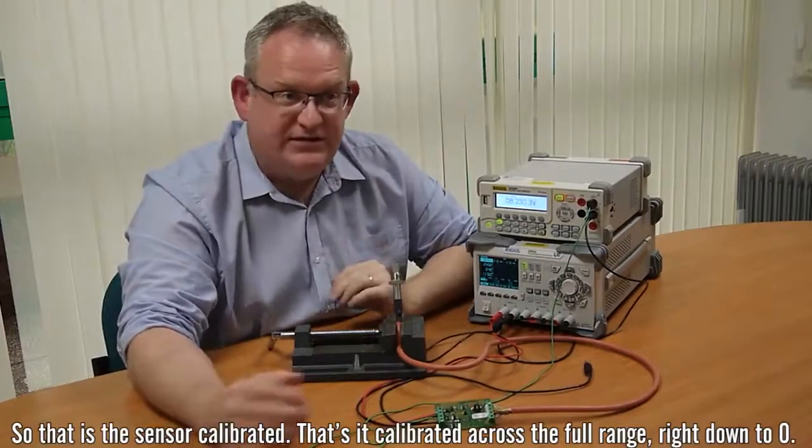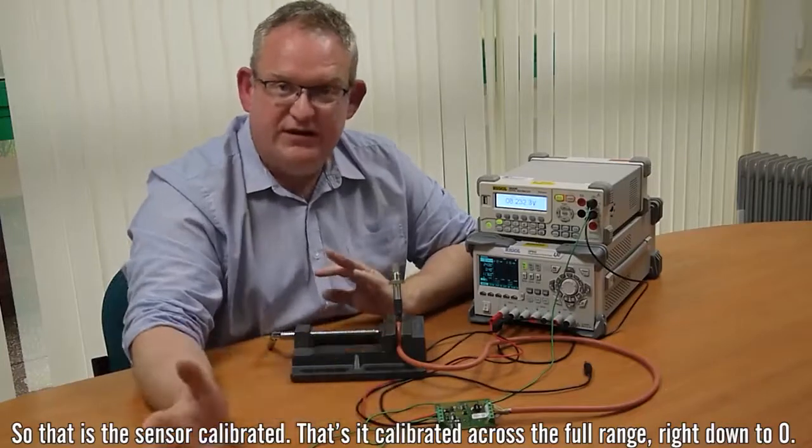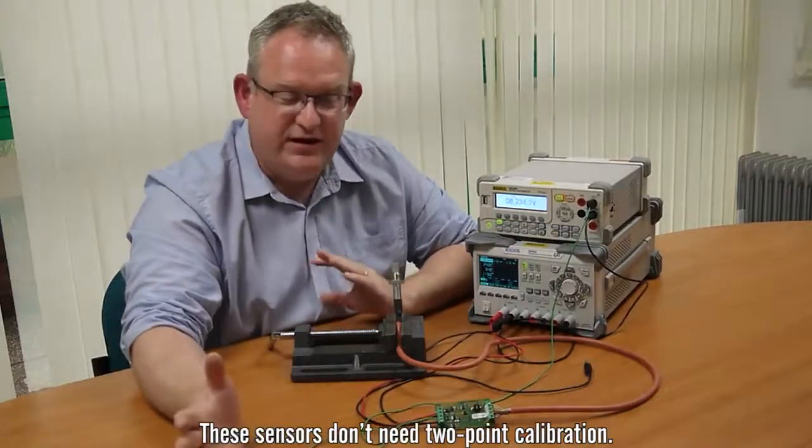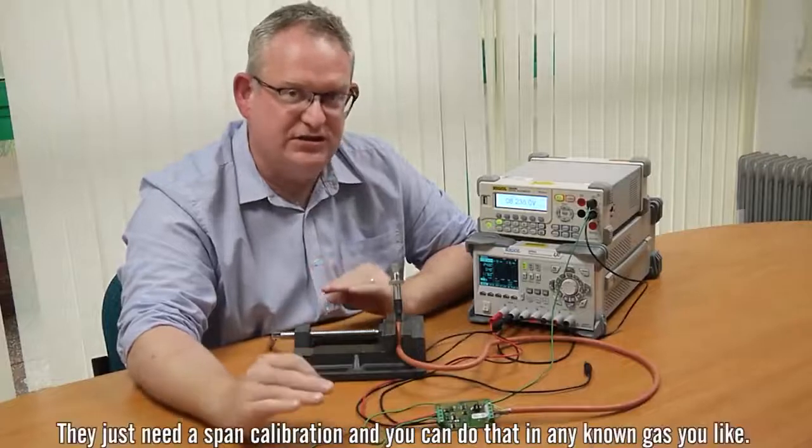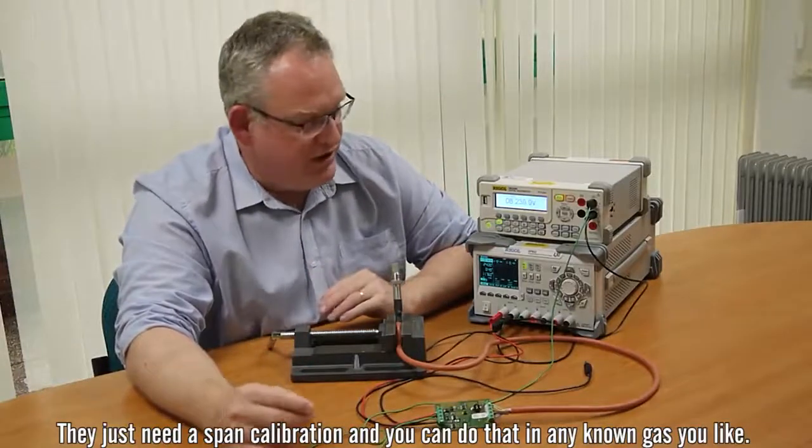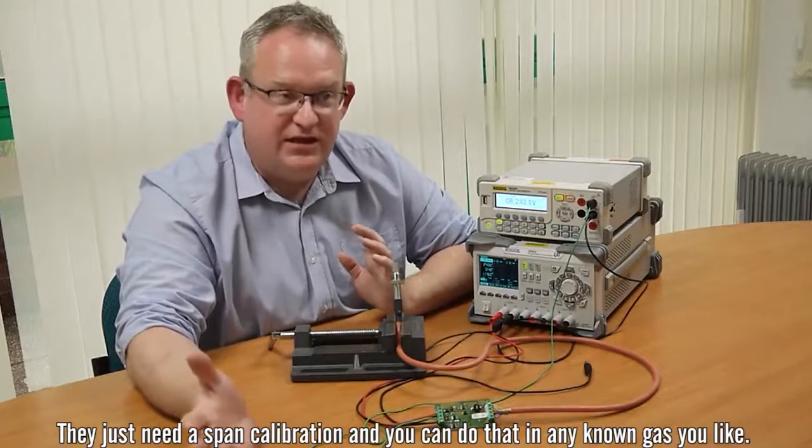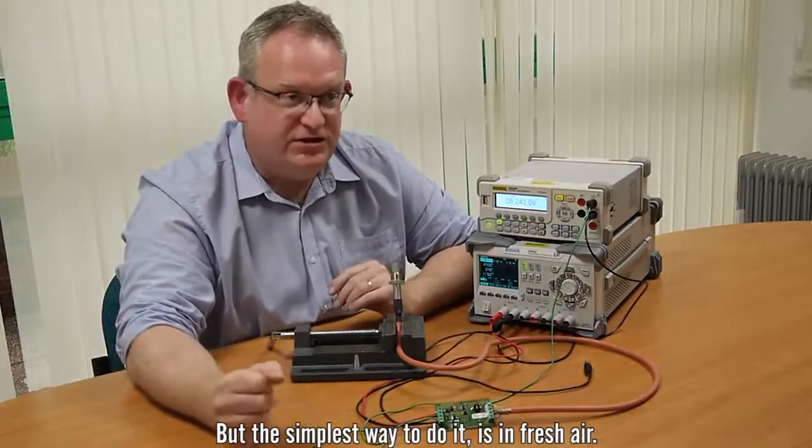So that's the sensor calibrated. That's it calibrated across the full range right down to zero. These sensors don't need two point calibration. They don't need the zero or an offset calibration. They just need a span calibration and you can do that in any known gas you like but the simplest way to do it is in fresh air.